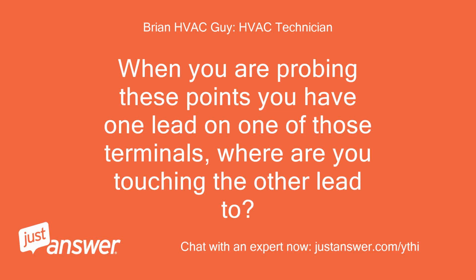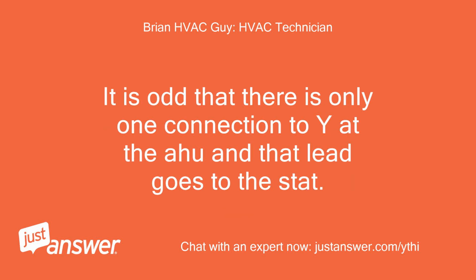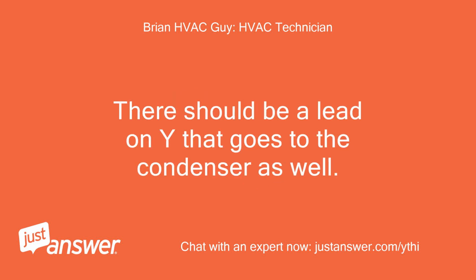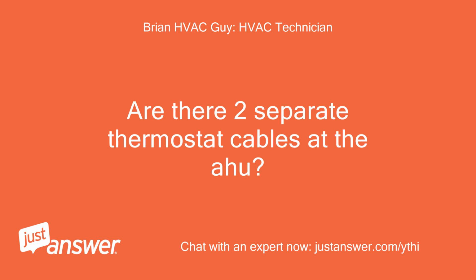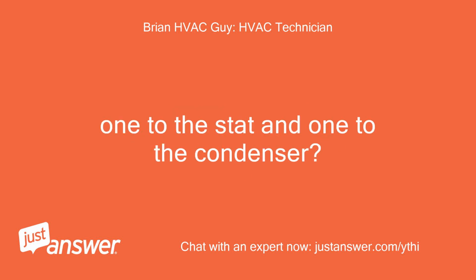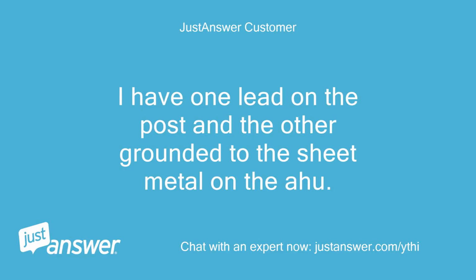When you are probing these points, you have one lead on one of those terminals. Where are you touching the other lead to? It is odd that there is only one connection to Y at the AHU and that lead goes to the stat. There should be a lead on Y that goes to the condenser as well. Are there 2 separate thermostat cables at the AHU? One to the stat and one to the condenser? I have one lead on the post and the other grounded to the sheet metal on the AHU.